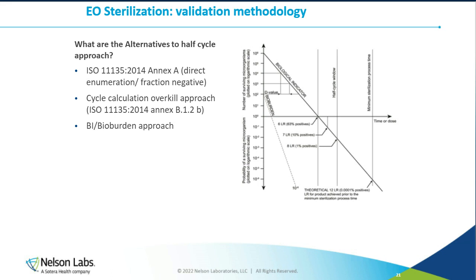But still in overkill, we have the Annex B of the standards, the B12B section that is using the cycle calculation overkill approach. So it is still an overkill based on biological indicators, but it can allow a few positive BIs, and we can not just double the time, but do some mathematical calculation to have the D value assessed, and then we can have the 10⁻⁶ by calculation. And lastly, we can still use the BI bioburden approach, in which we can define a maximum bioburden, and instead of having 12 spore log reduction, we could live with 9 if the bioburden is limited, as an example, at 1,000 CFUs.